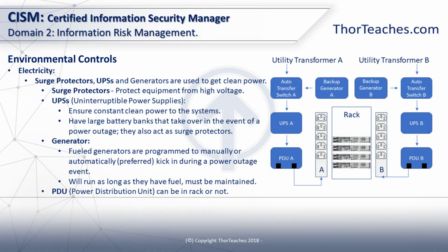Over here on the right, you can see a graphic that will show a very simplified version of how we can have this and how the logical flow of the power would look in our data center. So the utility transformer A is the power company. That's where they send power into our system. We would then have an auto transfer switch, which has the backup generator attached to it. If the utility provider goes down and we have a blackout, the backup generator gets told to start producing power. The transfer switch feeds into the UPS.